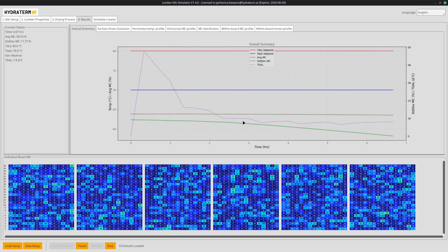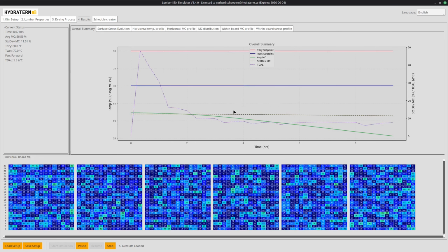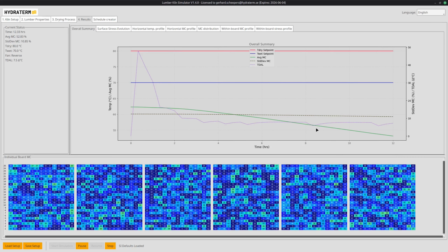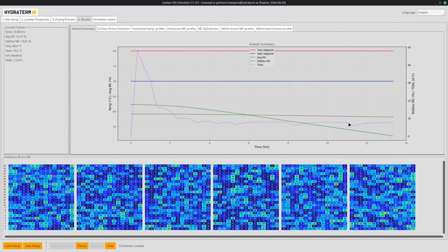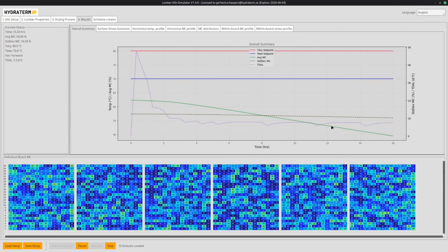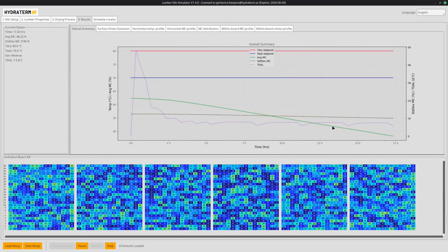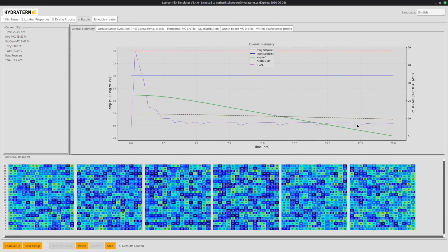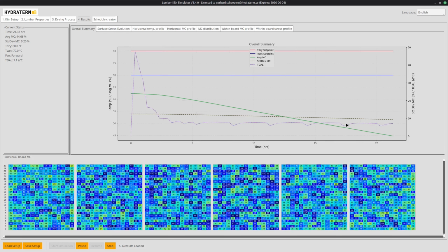Now we will focus on the temperature drop across the load. It is this purple line in the graph and you can see it varies with airflow changes. There are dips in the temperature drop across the load when the fans reverse. So we want to find values that are outside the dips or fan reversals.